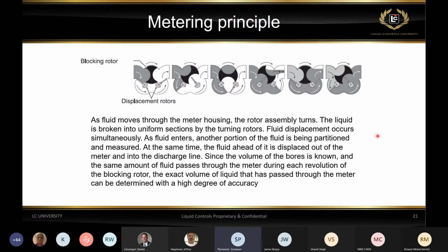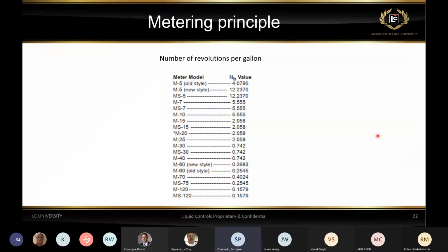And how much liquid does it move through per each revolution? Well, that will depend on the size of a meter. The bigger the meter, the more liquid moves through per each revolution. This little chart indicates how many revolutions it takes to displace 1 gallon. We can recalculate that into liters if necessary by dividing this by 3.785.